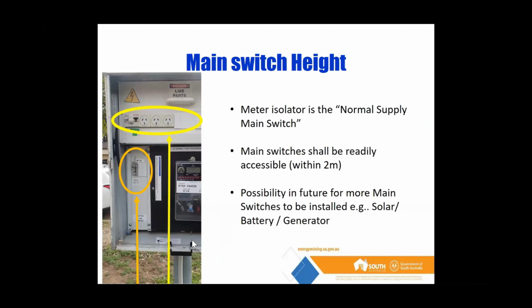Something that we're starting to come across quite commonly now is obviously solar, batteries, generators, other sources of supply. Now those sources of supply require a main switch. So a solar supply main switch, inverter main switch, etc. And 3000 talks about the requirements of main switches, and they all actually have to fall under that. So in this scenario, if we're looking at here, this switchboard's actually compliant. But if we look at the meter isolator there, the meter isolator, let's say, is just within 2 meters. So we're compliant because that's considered as our main switch here in South Australia.